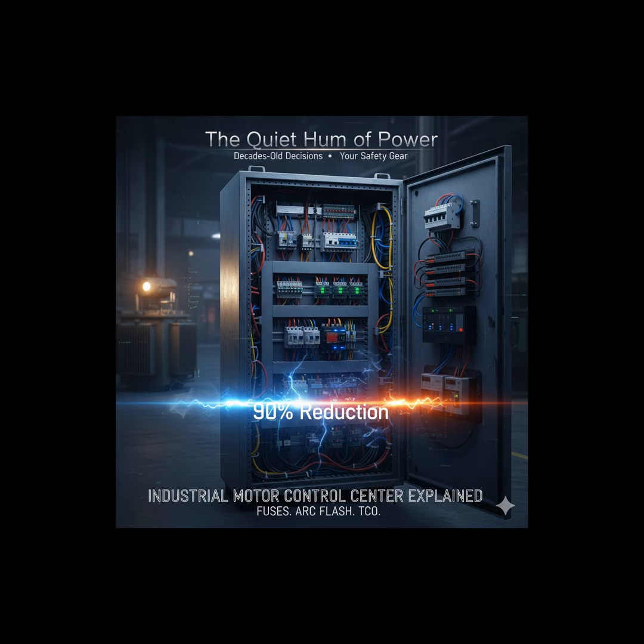Okay, let's unpack that definition, because it tells us immediately why MCCs dominate heavy industry. Why consolidate all this control into one place instead of having disparate components scattered near every motor? It really boils down to efficiency and scalability. When you centralize, you dramatically speed up installation and simplify all the wiring management. I can imagine. Instead of running heavy control wires all over a massive building, you run power to one central point. And for facilities that grow or change processes, it's so much easier to modify. So it's future-proof in a way. Exactly. You can add a new vertical section or swap out a starter unit for a bigger horsepower application without tearing up half the building's infrastructure. It's literally built for expansion.